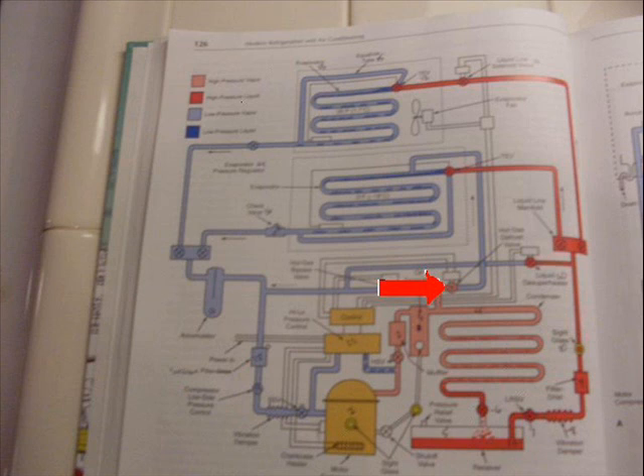And you don't want it to go back to the compressor, so hot gas always has an accumulator. There is an inverted P-trap to make sure no liquid leaves the evaporator and runs down that hot gas line, and we don't have any hot gas line that has liquid stuck in it. There's an inverted P-trap on the top. That's a plumbing device. It's a loop, an overpass, to make sure we don't have any liquid go back down that hot gas line. It's a little inverted trap, and it makes sure no liquid can get back, because it comes in deliberately on top of the tubing. So, no liquid can go back when we're normally operating. So, if you decide to draw the hot gas, make sure you put that P-trap on it.